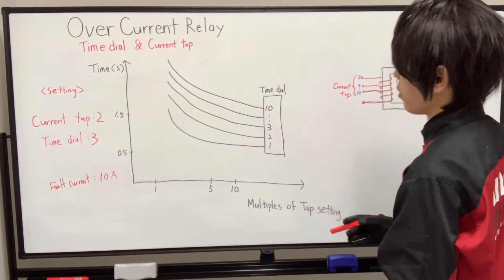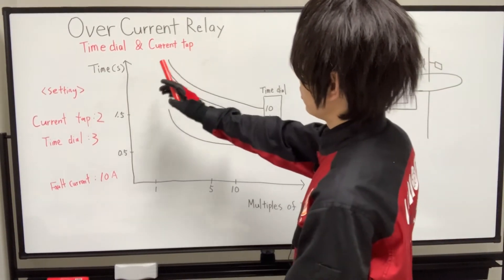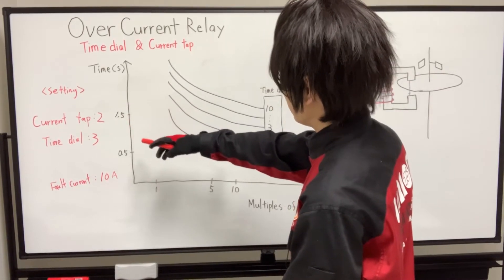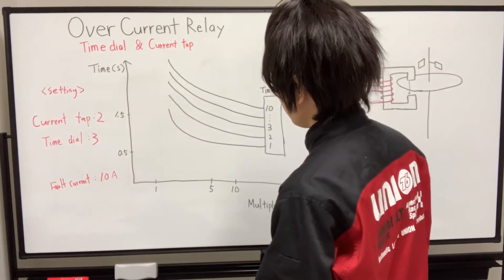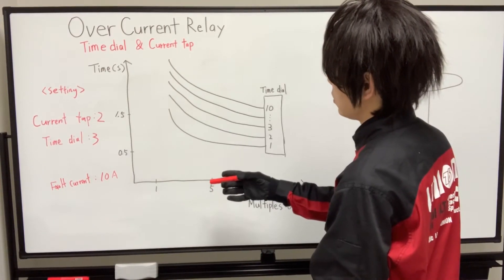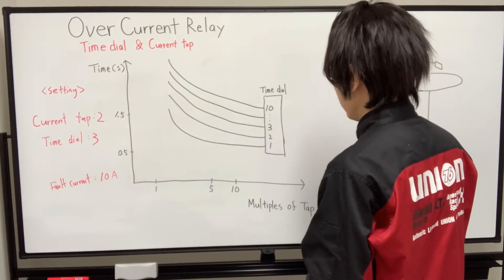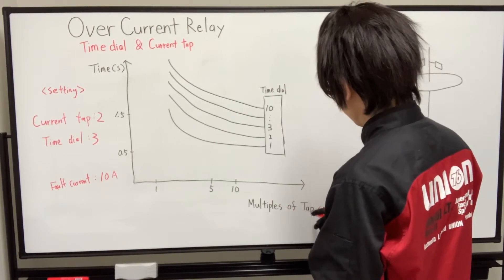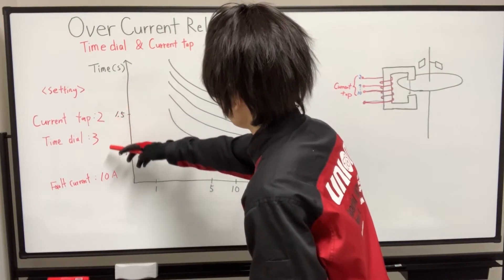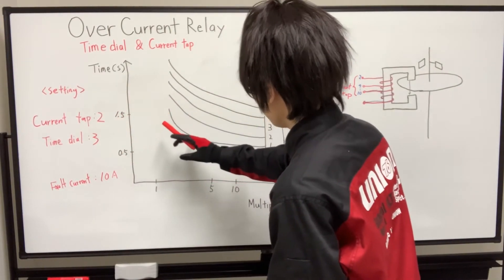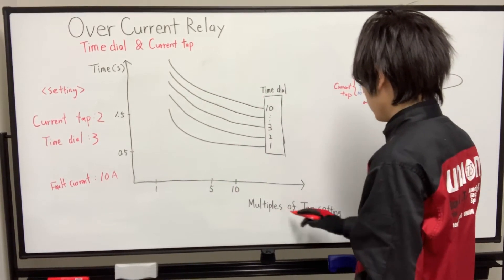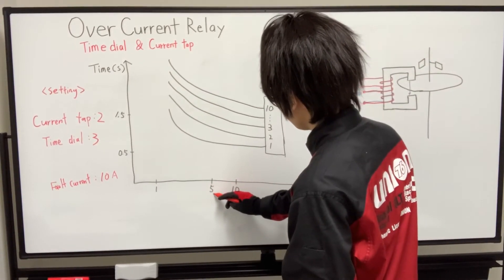OK, so for example, now the current tap is set to number 2, and time dial is set to number 3. And actual fault current is 10A flowing. So the multiple of tap setting - current tap is 2, fault current is 10A, so 5. 2 times 5 is 10A, so the multiple of tap setting is 5.